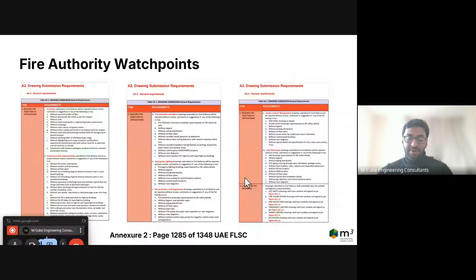Here's another example for a fire pump, where the authority, during the initial design stage for a super high-rise building, received a drawing showing only a single electrical pump, not a diesel pump. It was submitted, and the authority rejected it as non-compliant with NFPA 20, the standard for pumps and building classification. These are some of the things that can give you a direct rejection.